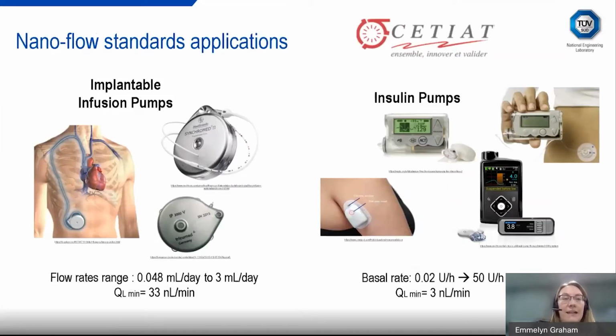These are some examples of nano-flow applications that will go down to nano flow rates. So the first one is implantable infusion pumps, and these can be used to deliver medication, different drugs to very specific targets in the body. And because they're implantable and they'll deliver the medication to the target, it means you can use much smaller doses of the drugs. So these can go down to 33 nanoliters per minute in this example. Another example is the use of insulin pumps, and these can go down to very, very low flow rates in the nanoliter per minute range as well. These are becoming a lot more common to be used, and as the original example I showed you, there was an actual issue with insulin pumps which did cause significant safety issues for the users. So you want to make sure you have confidence in using these devices.